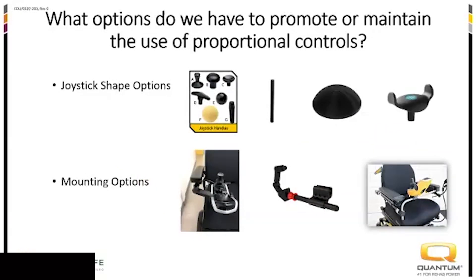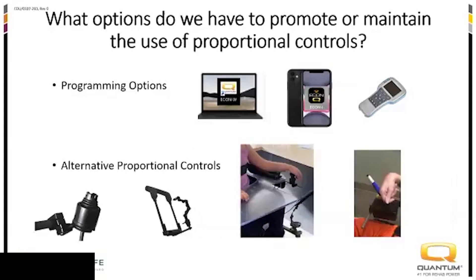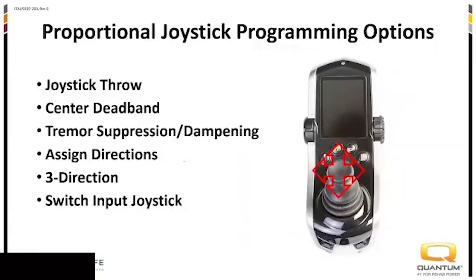Options to promote and maintain the use of proportional controls include joystick shape options, mounting options, programming options, and alternative proportional controls. For the standard joystick, programming features include changing the distance the person has to push the joystick for a full command, center deadband and tremor suppression or dampening for impaired motor control or tremors, and reassigning directions.